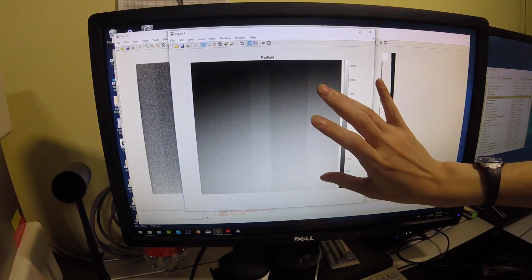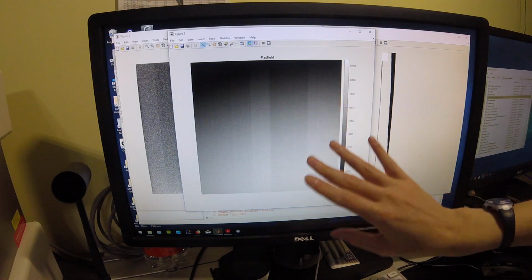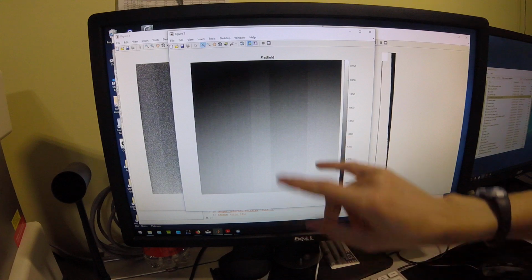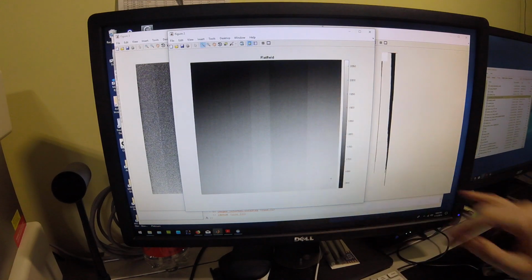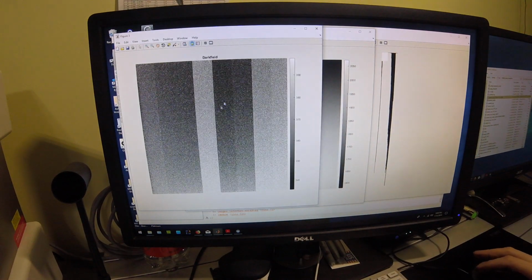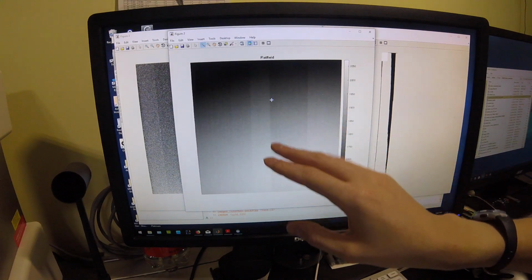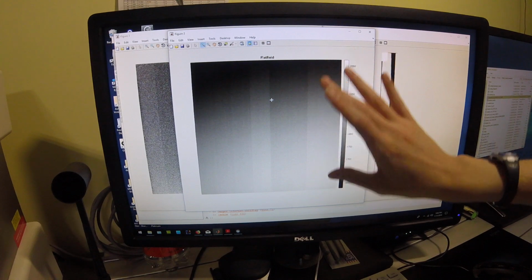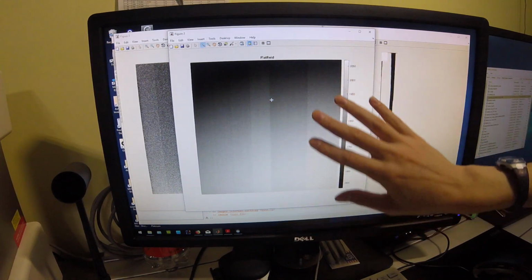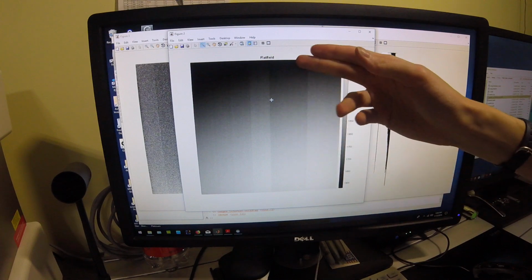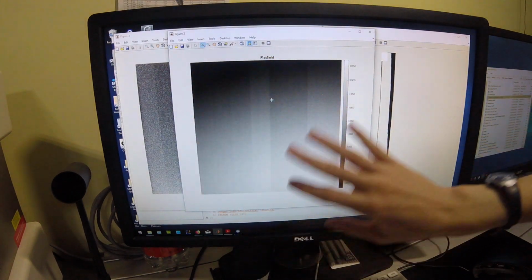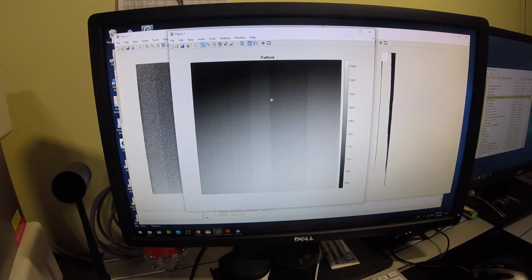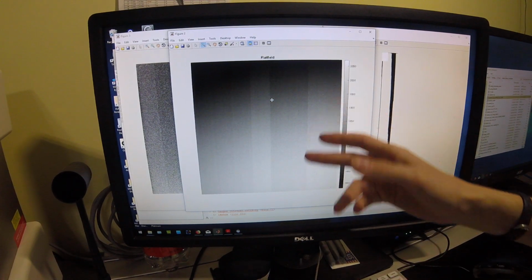So to perform that Flatfield Darkfield correction, what you do is you take an image of an actual object. You would subtract the Darkfield, which removes any dark current, and then you divide that by the Flatfield minus the Darkfield. So that would compensate for that inhomogeneity in any X-ray beam effects and in effects of the sensitivity of the detector and the carbon fiber plate. So that would give you a much clearer image. So that will substantially reduce the noise in the X-ray system.